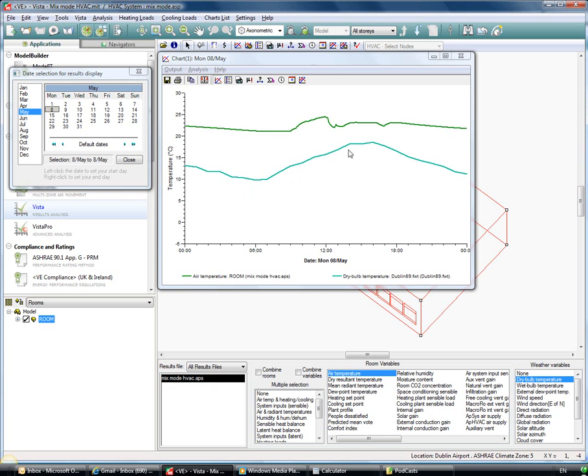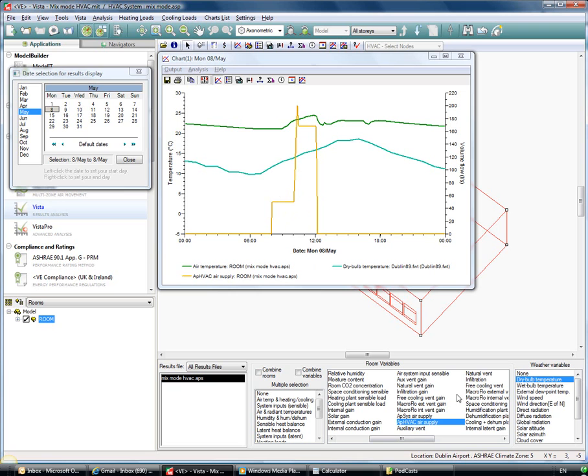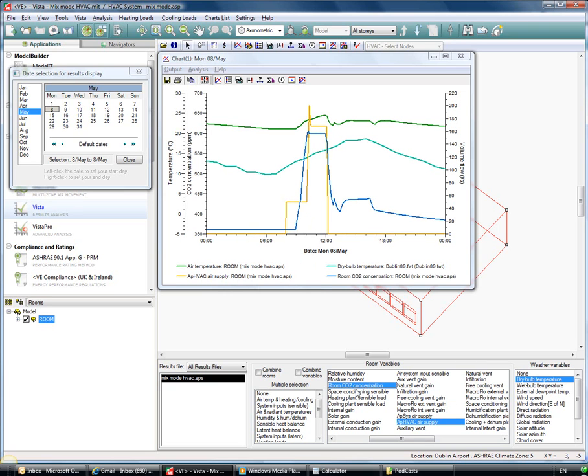So as we look at it, I can choose Apache HVAC air supply. And sure enough, once it's below 16 degrees I can see my HVAC supply coming on, starting out at that minimum limit which I set of 50 liters per second. And then once the CO2 in the space goes up, so as I choose room CO2, once the CO2 in the space goes up above the 575 limit, our system starts to ramp up towards the 300 mark that we had set in terms of liters per second.